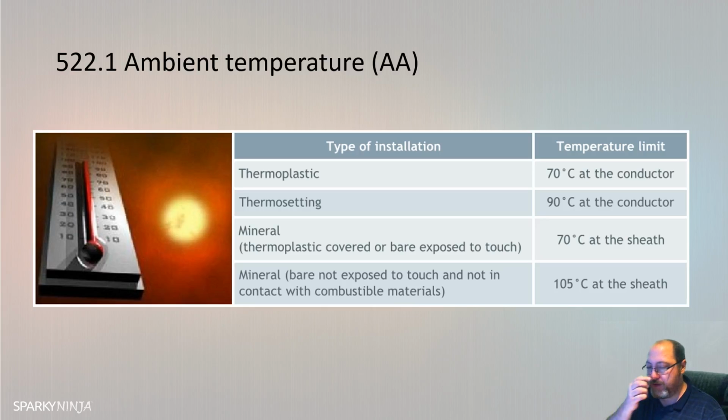So if I was to say the classification of external influence for an ambient temperature of plus 5 degrees C, plus 40 degrees C, you'd be going AA5. So the reference is fairly obvious once you understand that there are three columns there. There's AA for ambient, and then there's AF for corrosion. Then you have AM for electromagnetic. Going across, there are three separate columns.